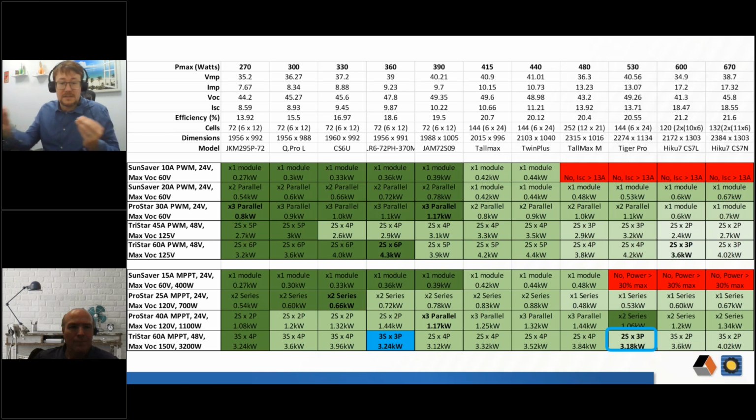If you have conflicting design influences where you need a certain amount of power, but you also need a certain weight limitation, lithium can be a great option. The other one is if battery replacement costs are outrageous. If you're sending PhDs via helicopters to the top of a mountain and you need to do that 5 years into the project, but it's going to be a 10-year duration, you may very well be better off putting in a battery from the get-go that doesn't have a planned maintenance replacement interval.